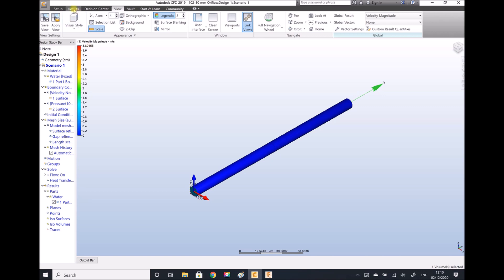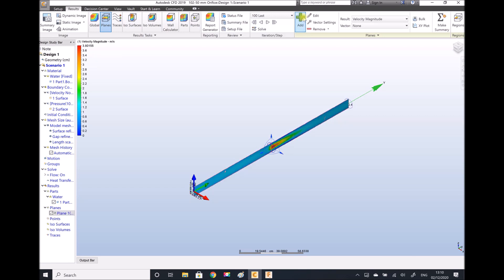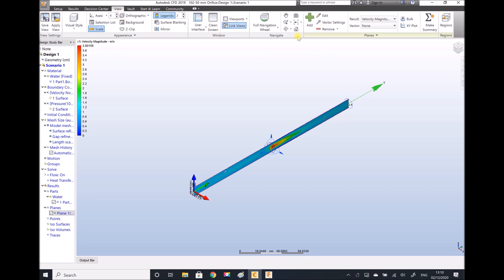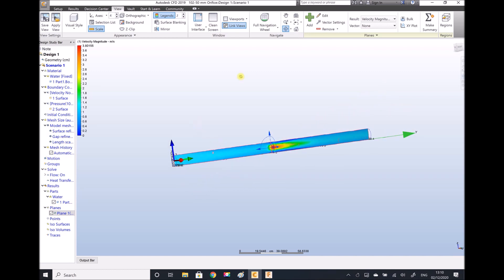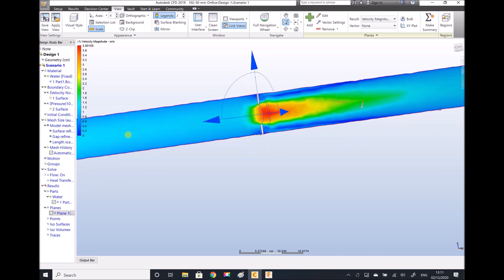If we select the Results tab and select planes, we're going to create a view plane so we can see what's happening inside. If we click add, the software picks a logical view plane — a cross-sectional cut through the centre of our pipe. Zooming in, we can see the fluid travelling from left to right at 0.95 metres per second. Close to the wall the fluid velocity is zero, which is as we would expect due to viscous drag. And then as the fluid travels through the orifice, we see the velocity speed up or increase.